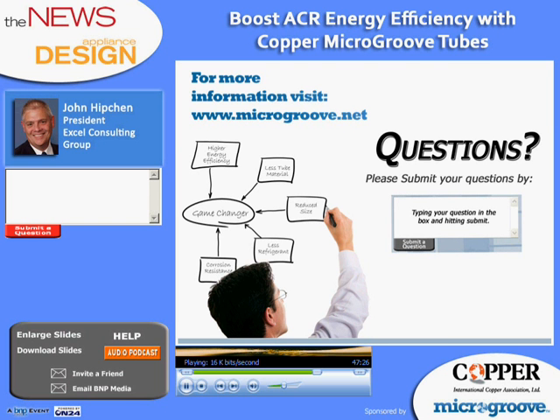Okay. One person would like to know, what about the oil? What is the effect of the grooves? The effect of oil in a refrigerant, it definitely does reduce slightly the amount of heat transfer that you can get, and we have studied data that demonstrates that. But you still have a much higher heat transfer with a MicroGroove tube than you would compared to a smooth wall tube, regardless of whether there's oil in the refrigerant or not.